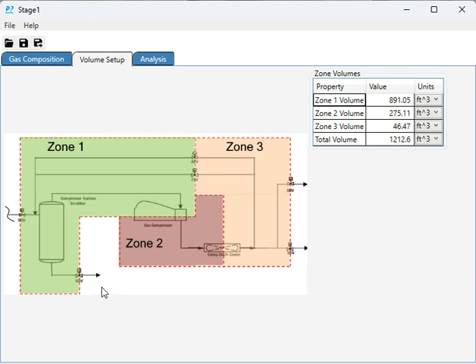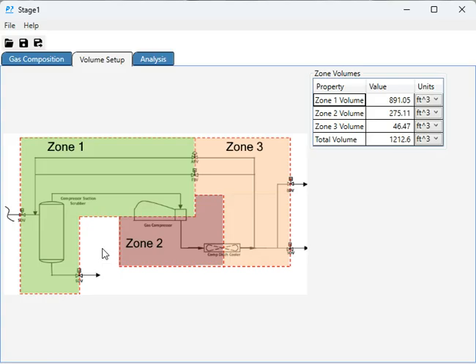but really the valves are so slow that the unit's going to settle out before the valves would close. So what you should be looking for to establish the boundary of the suction volume is the upstream check valve that would prevent flow going in the reverse direction of normal.